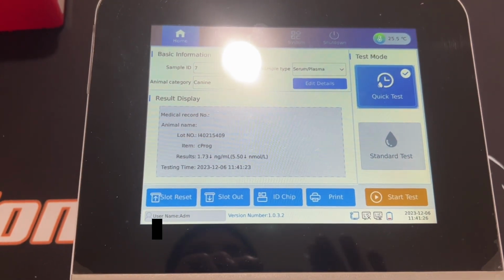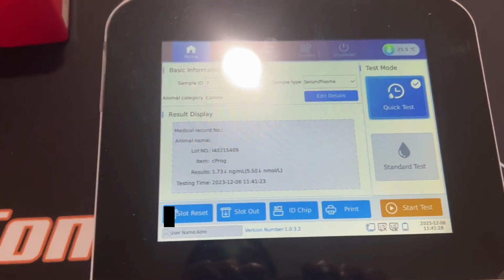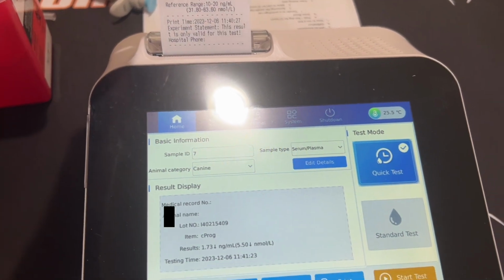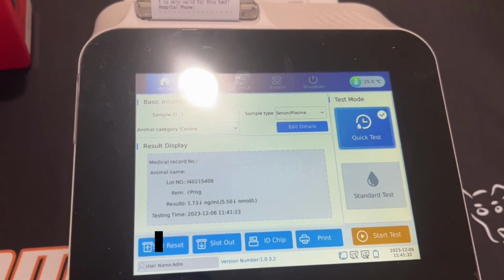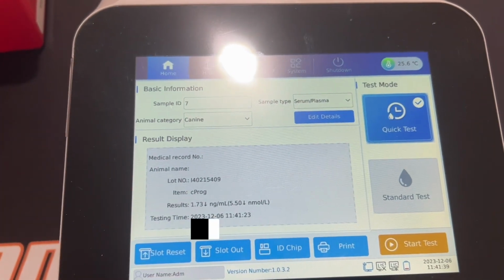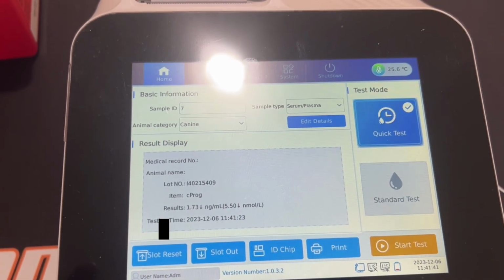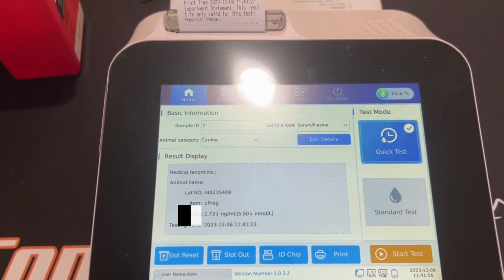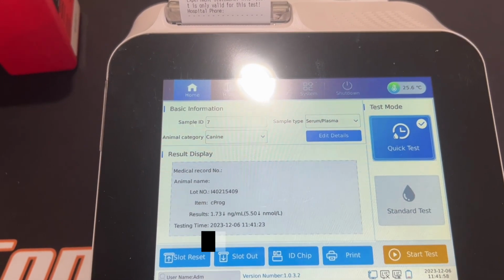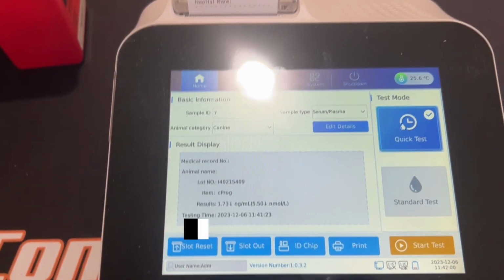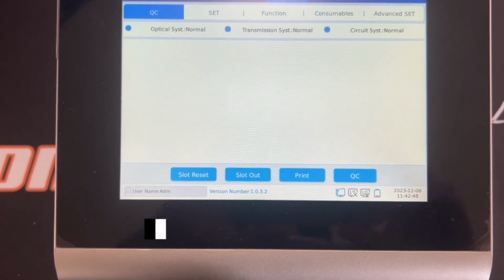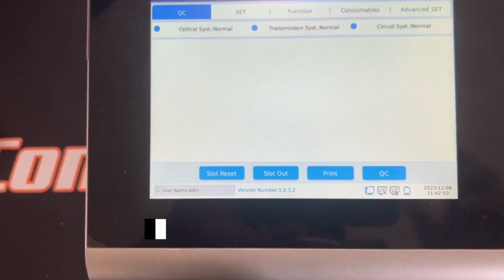1.73. So what you're looking for in this precision test is that all these results should be pretty much the same. They may be slightly different, but as long as they're close within a point of each other, that means your machine is reading precisely. If it doesn't read like this and there's a wide range on the results of your precision test, please let us know right away. The next troubleshooting test is the QC test.